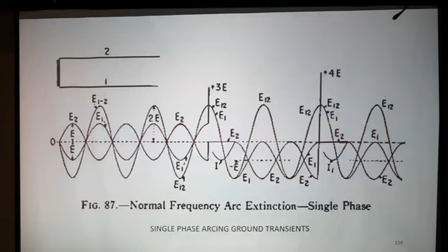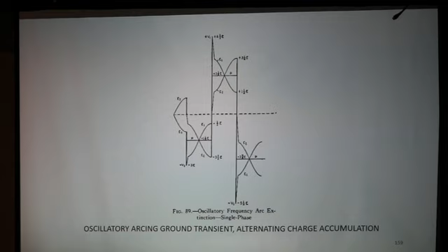This is the way the voltage magnifies: each time the arc jumps to ground, it charges the system one polarity and then the other, always leaving some DC behind, until the line has a rather considerable amount of voltage on it.